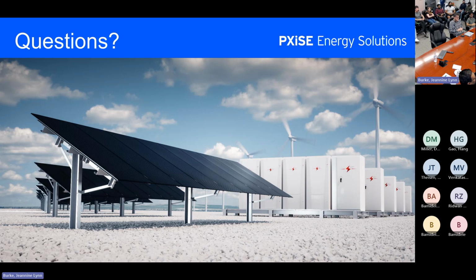This is the grid, and this is the angle of the microgrid. I have to drive this angle to within a bandwidth of the main grid angle. I do that with delta F commands to the grid forming inverter, and that will drive this up here. Now, this is an interesting control loop that Raymond and I also had debates about. How do you do this?